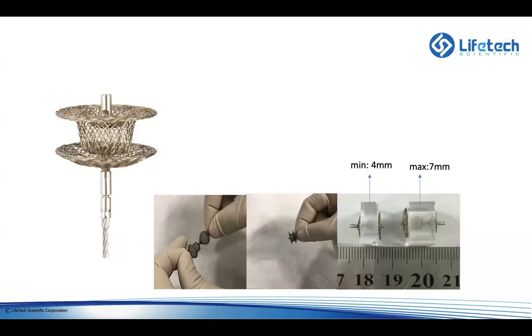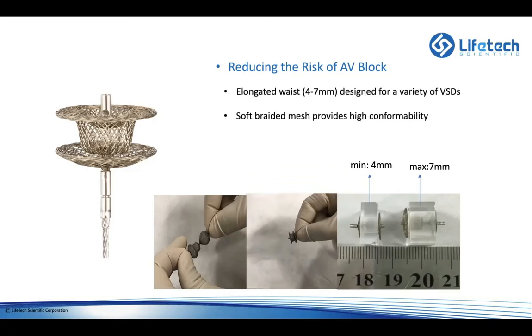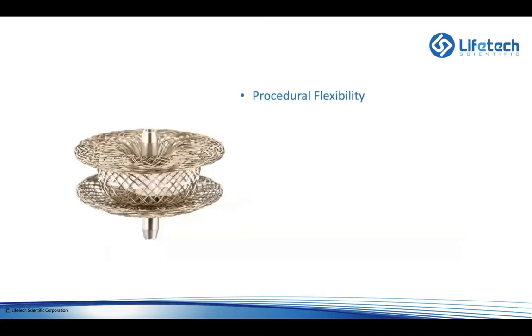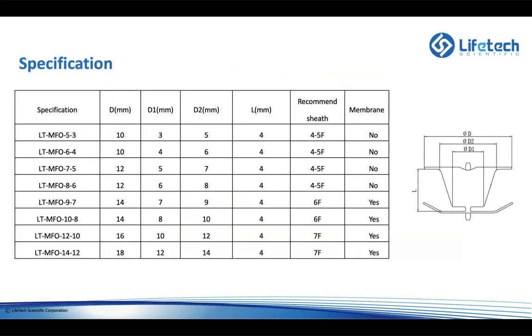And on the bottom right here, you'll see that it can go anywhere from 4 to 7 millimeters and really stretches out and flexible. And that, I think, is a huge advantage of this device, that rather than forcing a pressure onto the myocardium, it will actually move with the contraction of the heart. And I think that's one of the reasons that we have this reduced risk of AV block with this device, because it's not a stiff device rubbing up against and causing inflammation and irritating the myocardium. And the soft braided mesh, really, it's very conformable, and it's a great device. And so that allows us, with this double retention disc with the double-sided screw, that retrograde or antegrade approach. And again, I'll show the advantage of that.